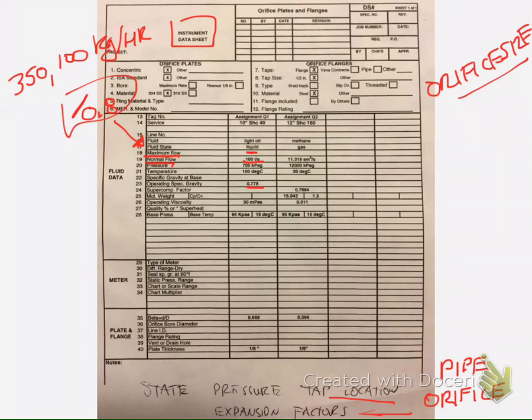So I'm going to go back to my program and key this in: 350,100 kilograms per hour. The density it's asking me for now is 778 kilograms per meter cubed, and line pressure, we can look that up here on our data sheet. It is 700 kPa gauge, and our calculator is asking for it in absolute pressure, so we need to add those two values, so 795.